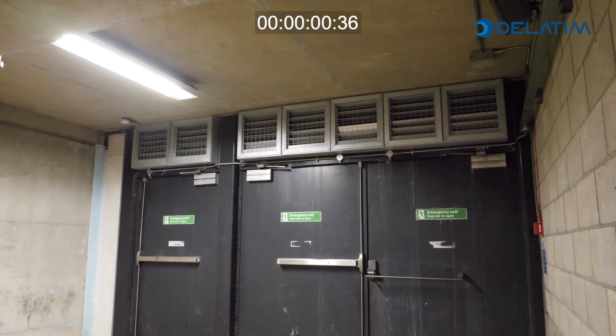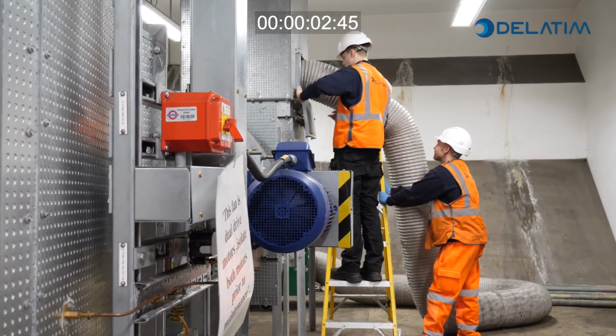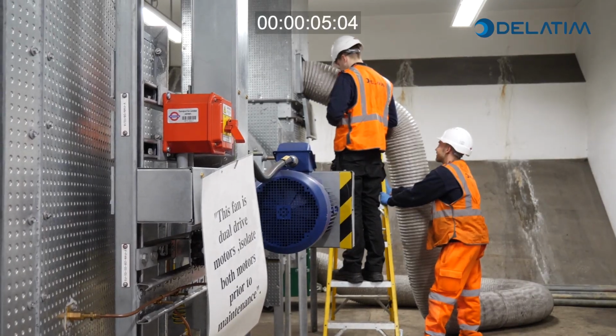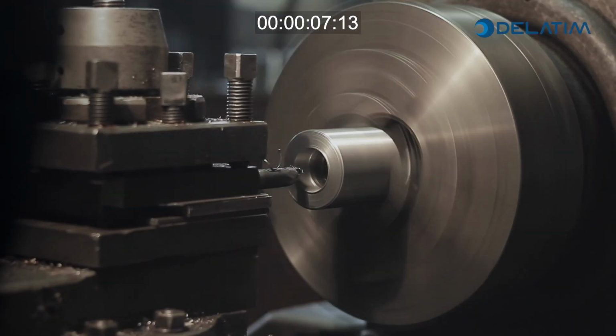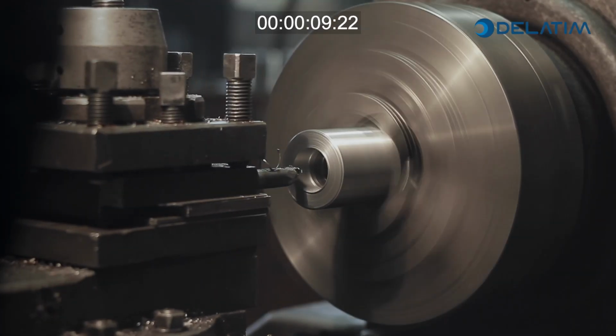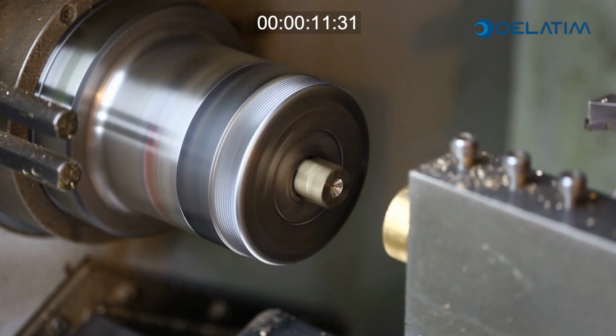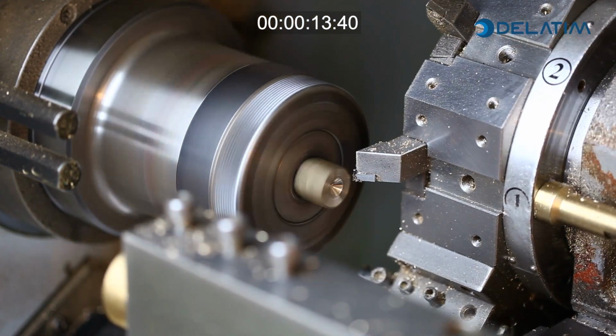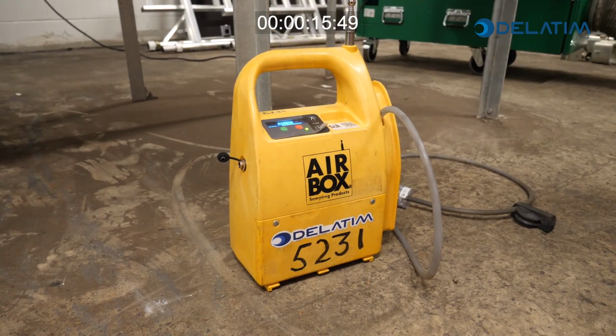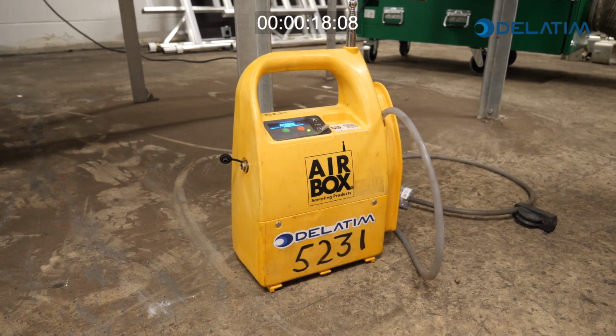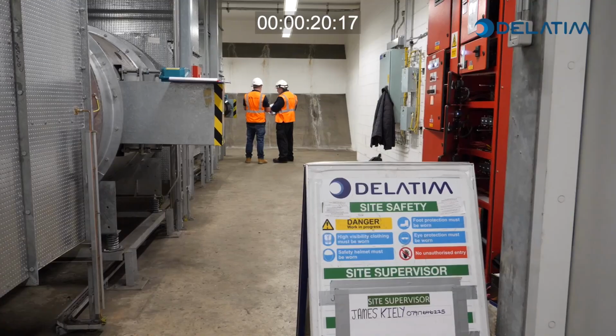Once the fan is disassembled, they are taken to the Browning's workshop. The fan bearings are removed, the shaft is set in a lathe and true running checks are made. The impeller is crack tested to be assessed for wear. It is then sent to a dynamic balancing machine to confirm balancing is correct.